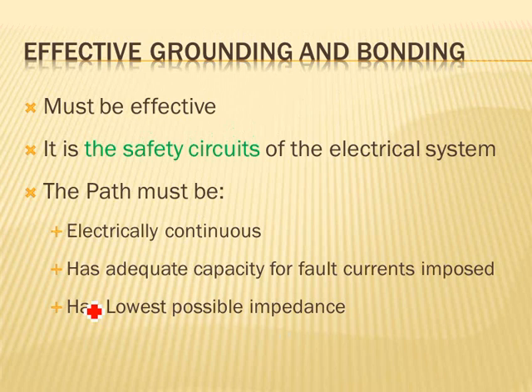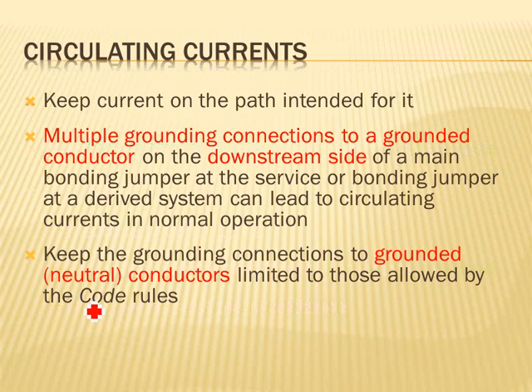The path must be electrically continuous and large enough to facilitate operation of the overcurrent device as well as the flow of the current. So it has to be continuous, current is not going to jump around, and it has to be large enough so the current can go fast enough through it to facilitate the operation of the overcurrent device.